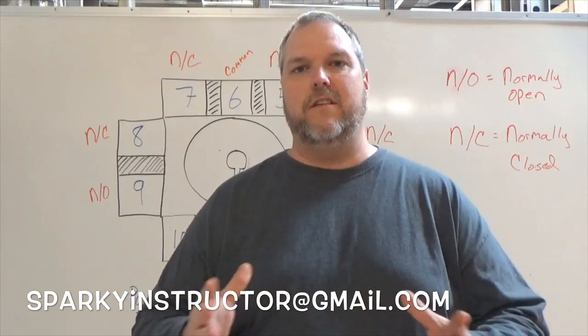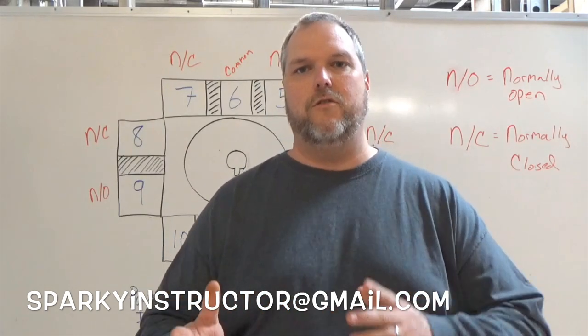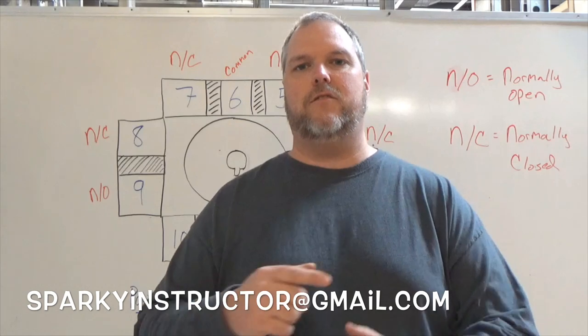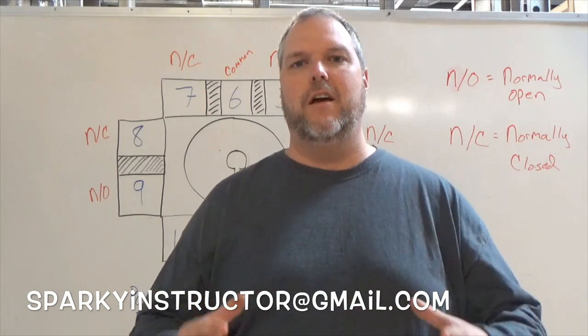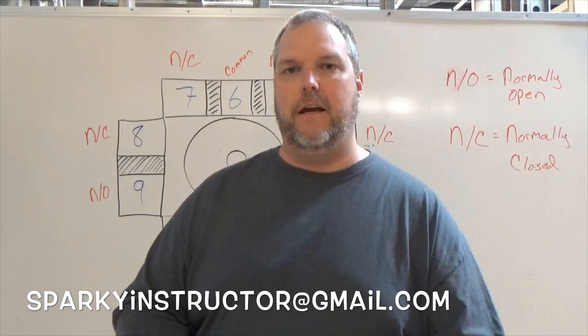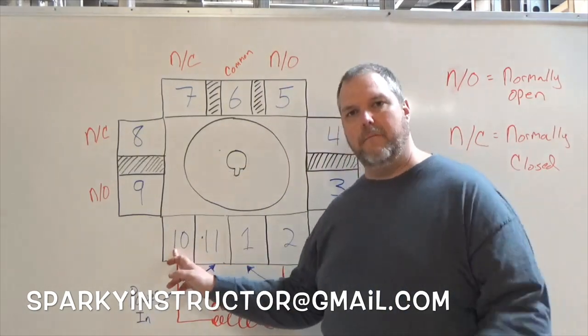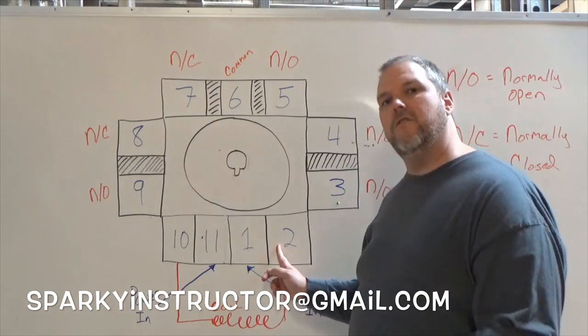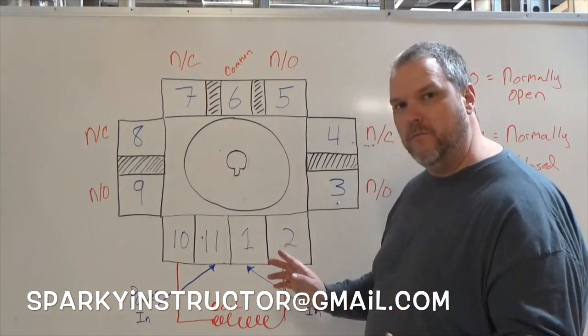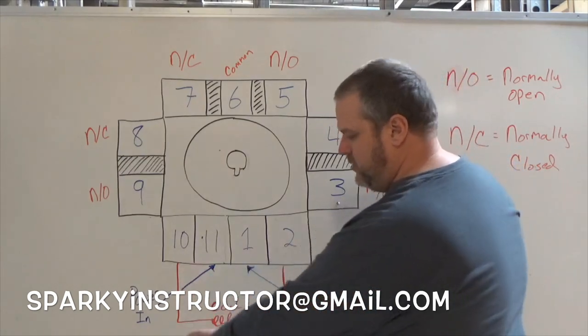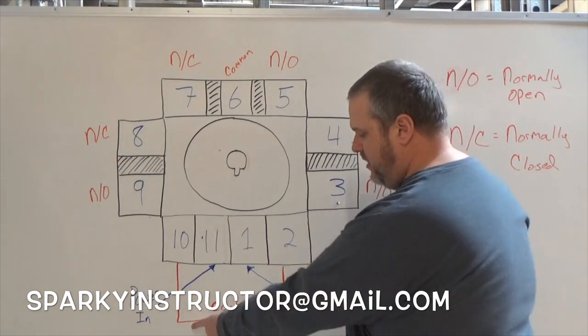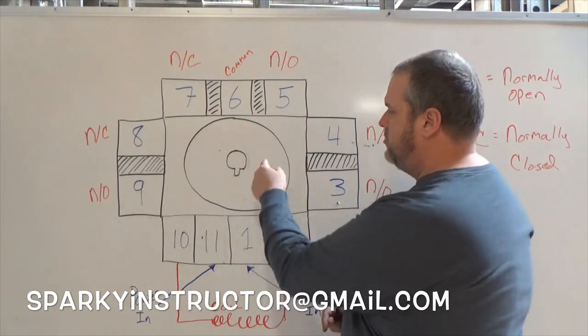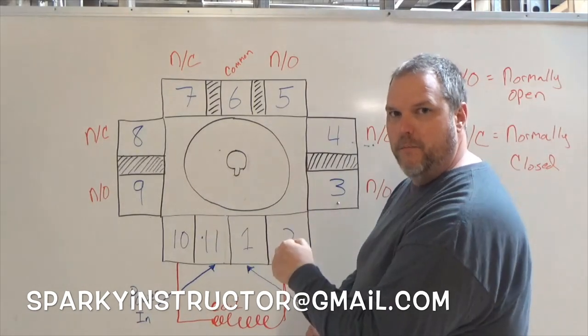These are 120 volt relays, so you can use the neutral or you can use the hot conductor, switch leg, whatever you're using to feed either 2 or 10. Meaning 2 can get my hot conductor or my neutral, but it can't do both. 10 can also get my hot conductor or my neutral, but again it can't do both. My drawing here is basically showing us that we have the coil. This is the coil, so this is what's going to energize and pull in to allow this pin to actually operate properly.